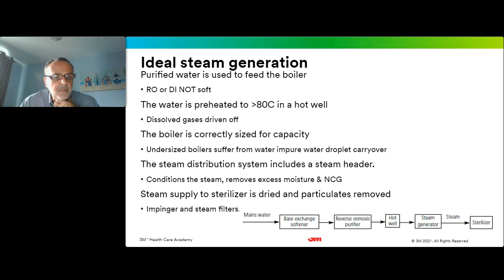It's very important to make sure that the boiler is correctly sized for the capacity of the sterilizers. If you have too small a boiler, then during maximum steam demand you get rapid boiling of the water, and this will create foam and lots of water aerosol carried over into the steam supply, which of course can potentially contaminate the steam supply. Ideally, the steam distribution system should include a steam header, and I'll talk about that in a second. And also, the steam supply should have a way of drying the steam and removing particulates.